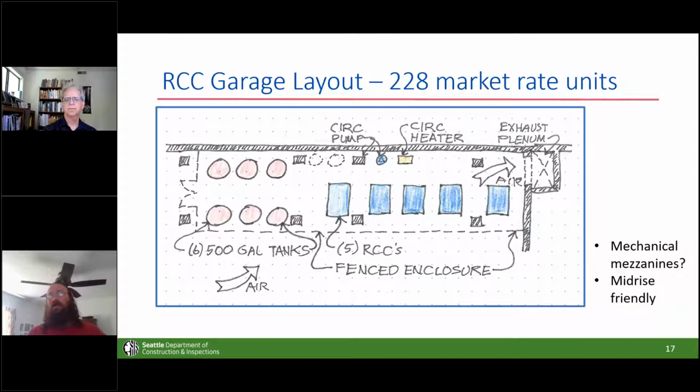High-rise projects would usually have, relatively speaking, postage stamp floor plates, so the CFM requirements are a good bit smaller for the garage exhaust. Sticking one of these in there would potentially mean larger than necessary garage exhaust shafts or larger than necessary discharge louvers at the alley. And those are always complicated to coordinate mechanically, as most of you know, I'm sure.